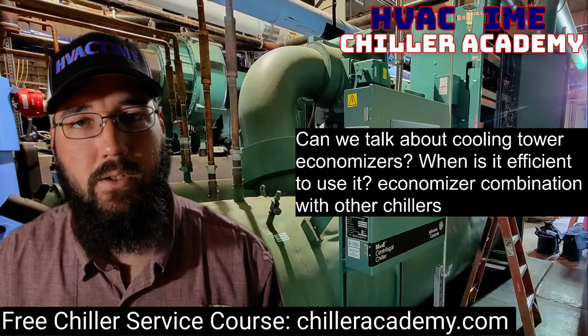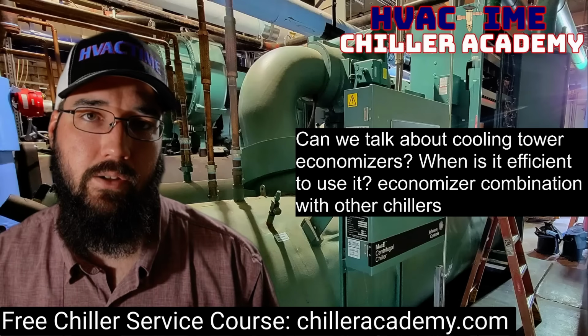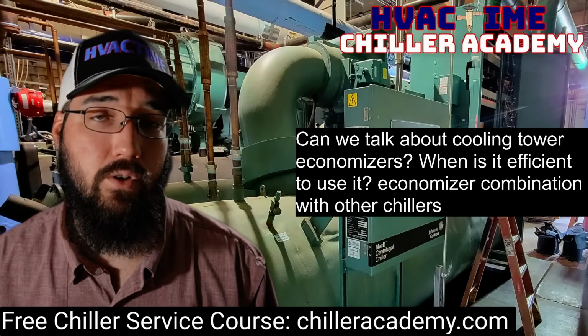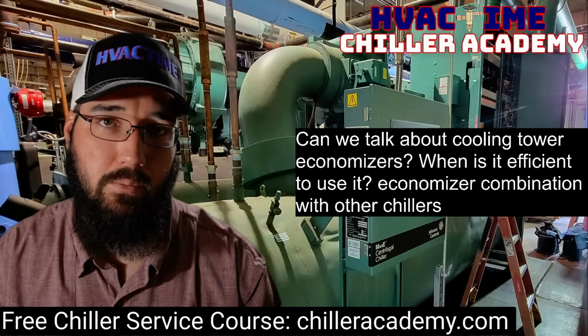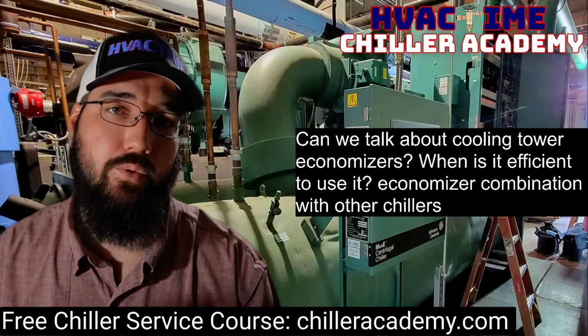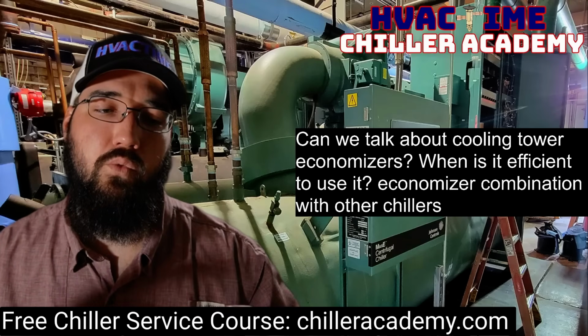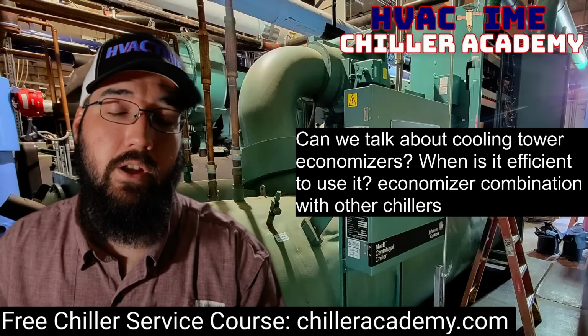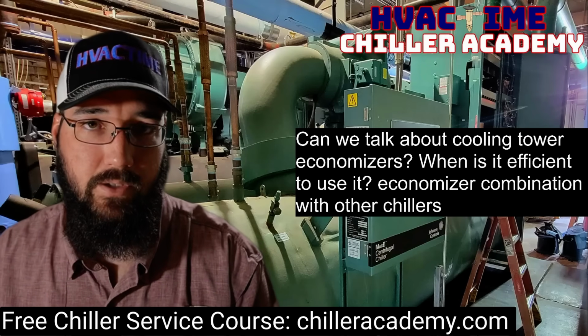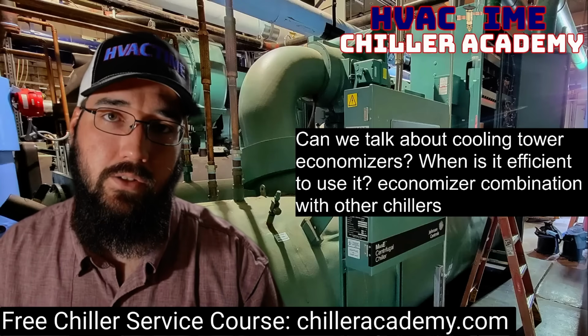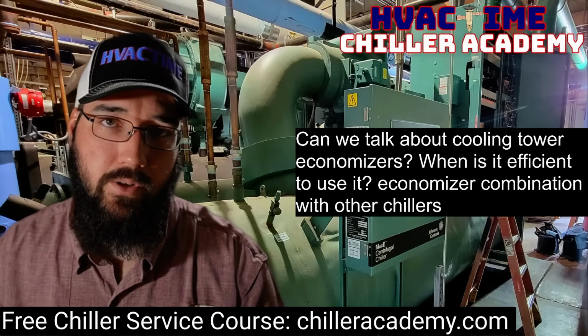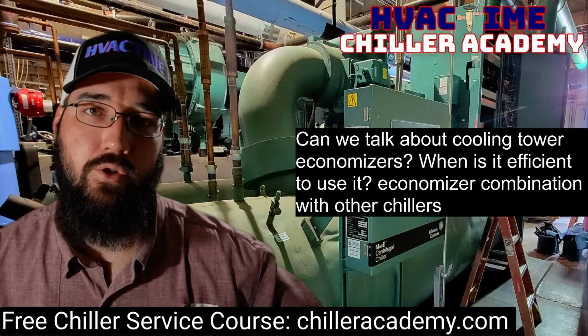And we need to be able to hit those lower end metrics with the tower given our wet bulb temperatures. We have to take in tower approach, things like that, in order to achieve that. And quite literally, our cooling tower becomes the cooling source for the building at that point. So we're using the condenser water through the cooling tower to chill our chill water loop.